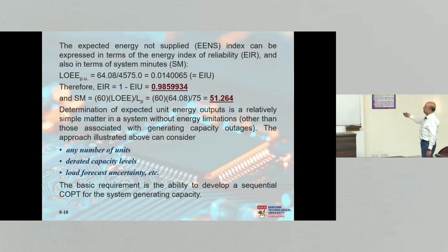So the determination of the expected unit energy outputs is a relatively simple matter in a system without energy limitations. But if the system is energy limited, then you have to consider that in your calculations. And the approach can also consider any number of units' derated capacity levels. We already saw that. One of the generators had derated capacity. And we can also include load forecast uncertainty, just like we did before the break. We did that for LOLE, but no reason why we can't do it for LOEE. It's the same. You have to do the calculations 7 times instead of 1 time.